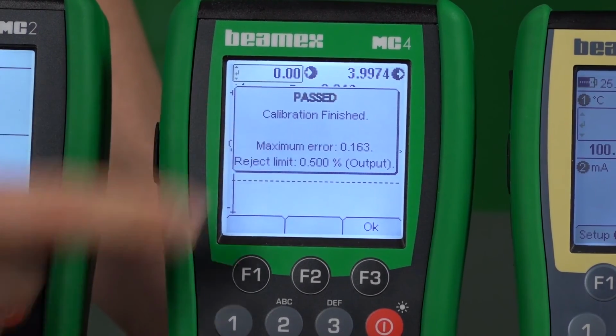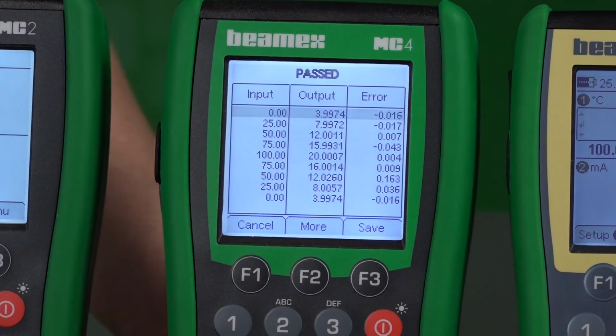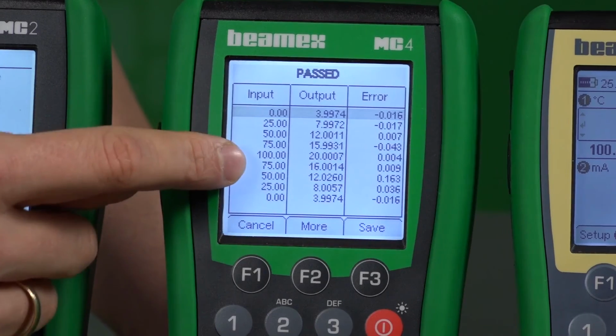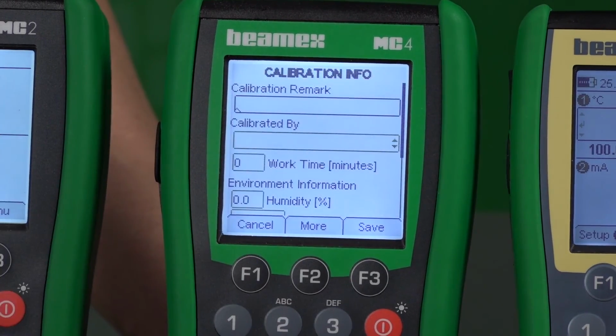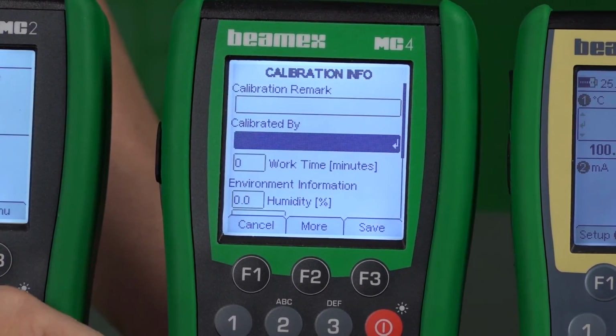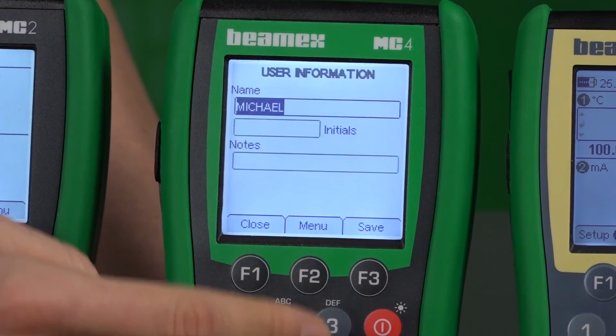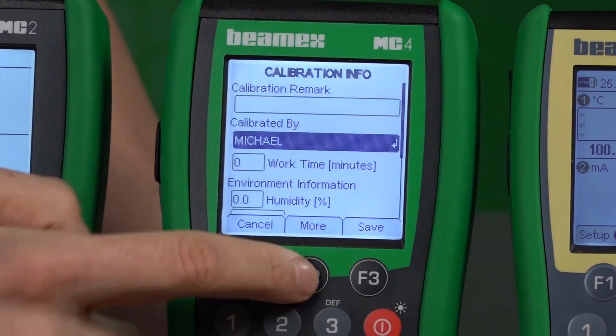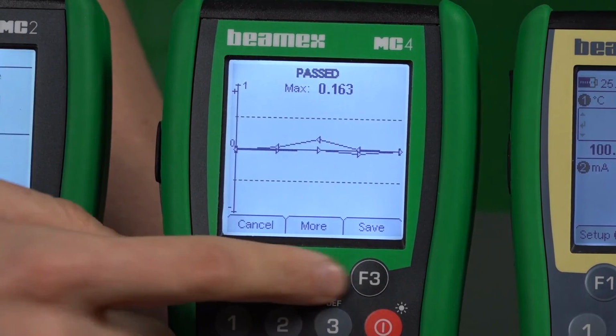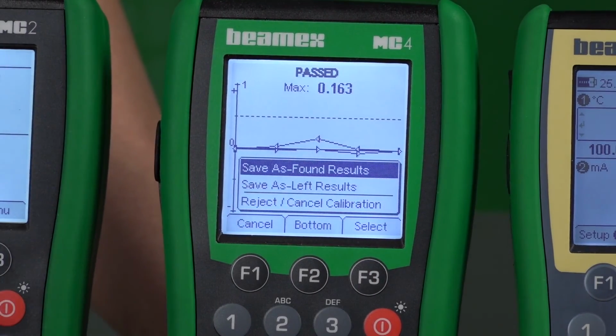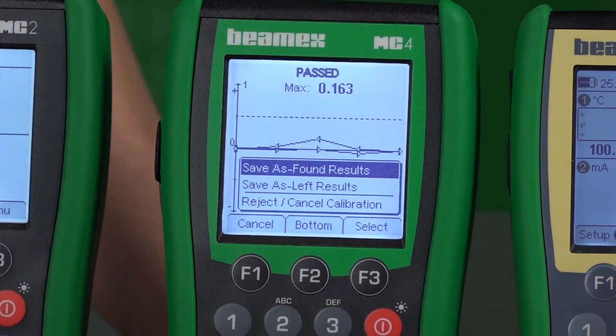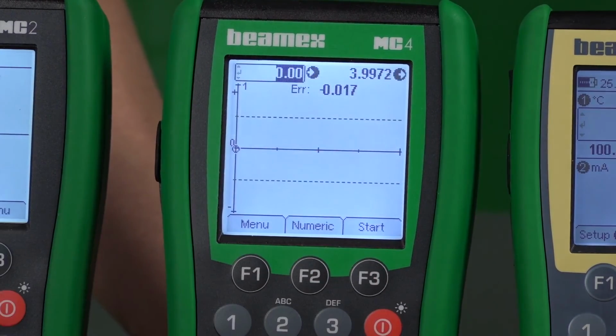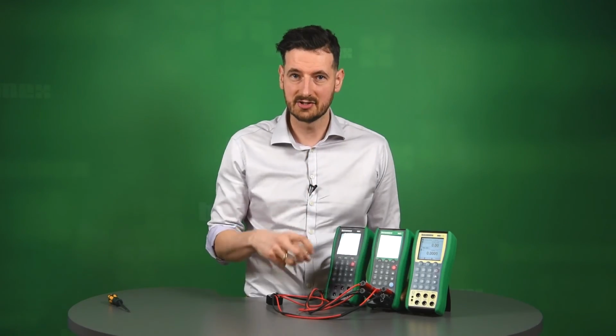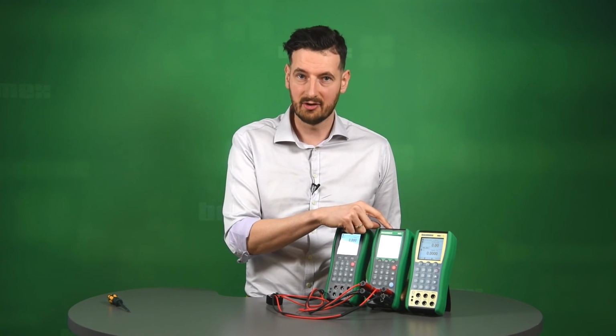You can see the maximum error. All you have to do is press OK. You can see the numbers here. You can click more. All I have to do right now is choose my name from the list. So that's what we're going to do. And also you can see the graph as we've seen before. Click Save, and you save this calibration as found, because that's what it was. You select, and right now this calibration has been saved into the memory of the MC4 and is ready to be transferred to the CMX calibration management software.